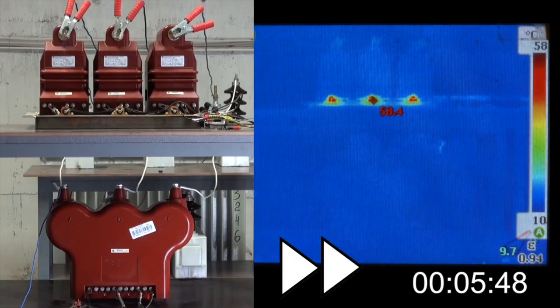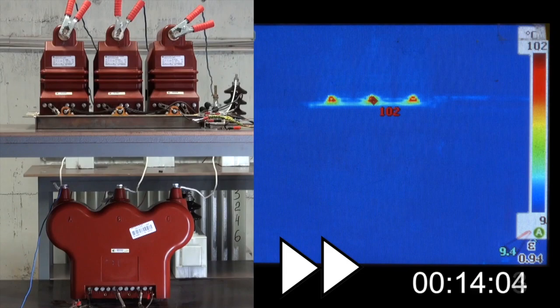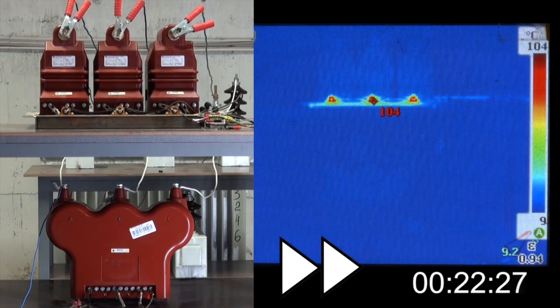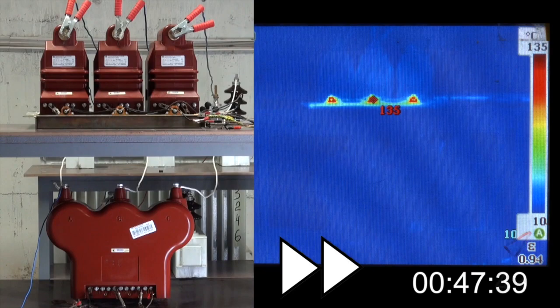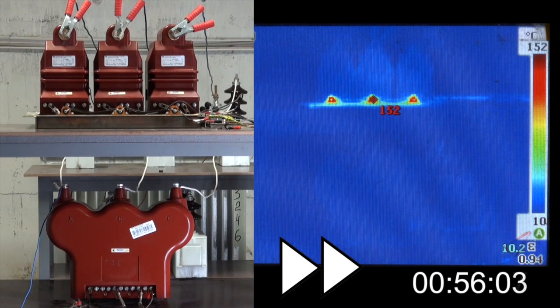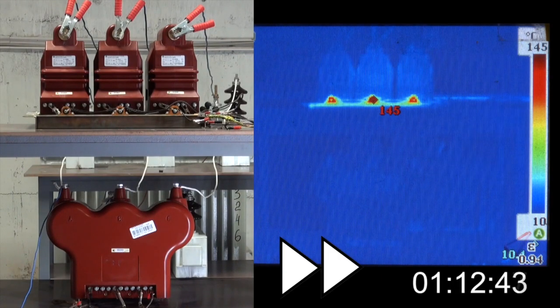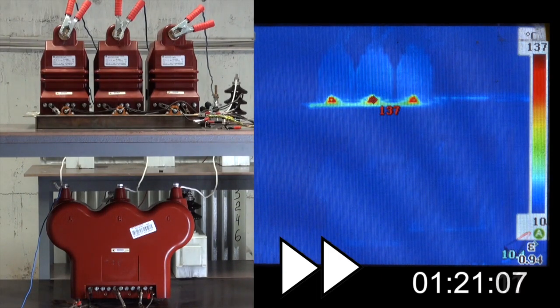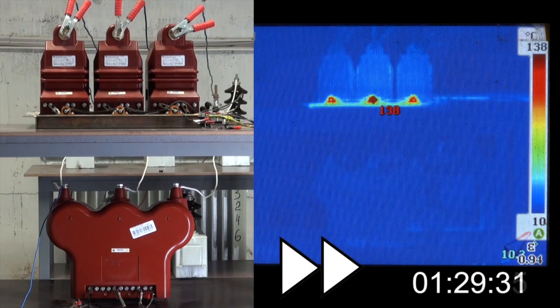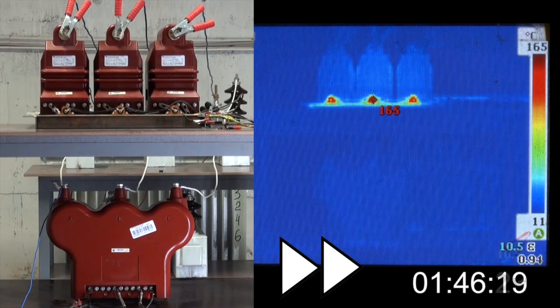The tests take place in real time. On the left half of the screen you can see the real view of the tested transformers, and on the right side a synchronous real-time picture of the tested transformers from the thermal imager. For clarity, the test time has been accelerated. From the very beginning of the test, the resistors, which are installed in the neutral of a three-phase group of transformers, are heated. The thermal imager allows us to see the actual temperature of the hottest point on the test object.